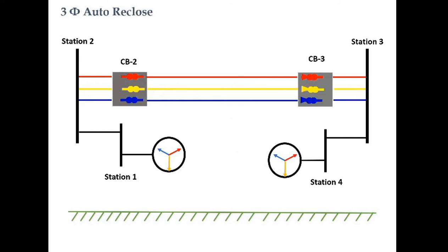Three-phase auto reclosure schemes are generally followed in substations where gang-operated circuit breakers are used. This type of scheme is generally used at the 132 kV level and below, while single-phase auto reclosure schemes are generally used at 220 kV and above level substations. From the figure, it can be observed that all phases of the circuit breakers are enclosed in a single enclosure — these circuit breakers are operated by a single mechanism. So for a single-phase fault, the whole circuit breaker — all three phases — will open, and for reclosure, all three phases will close together.